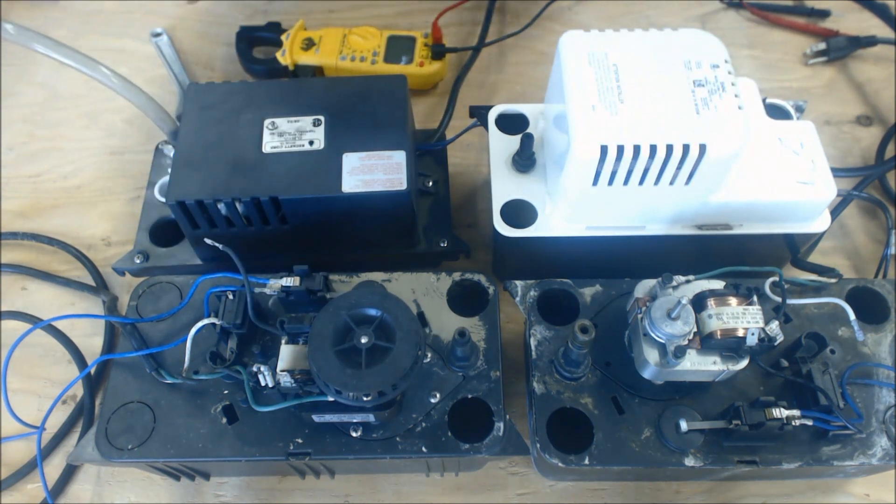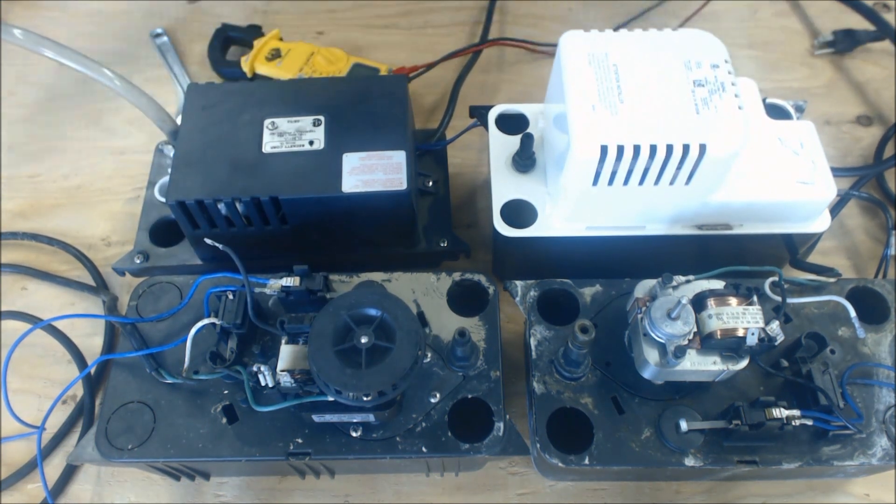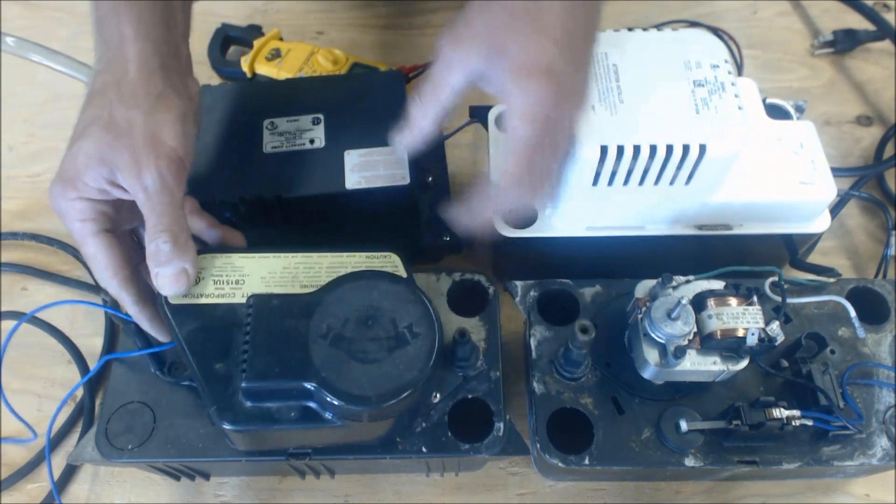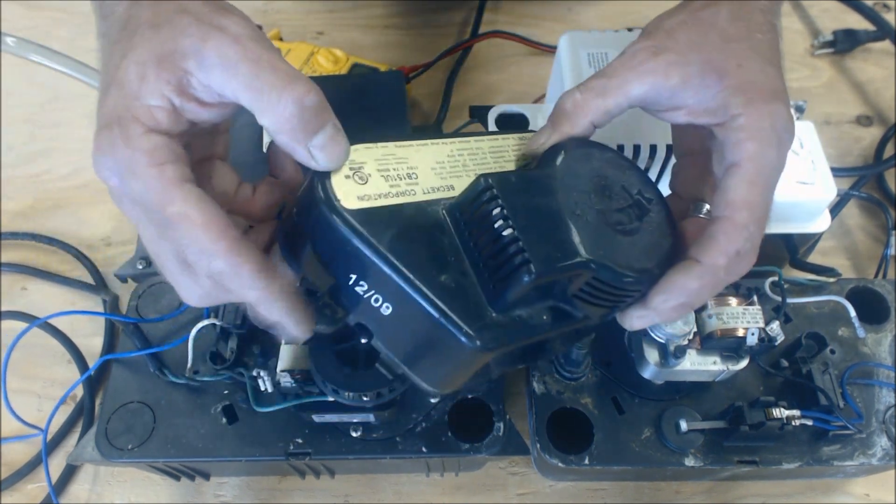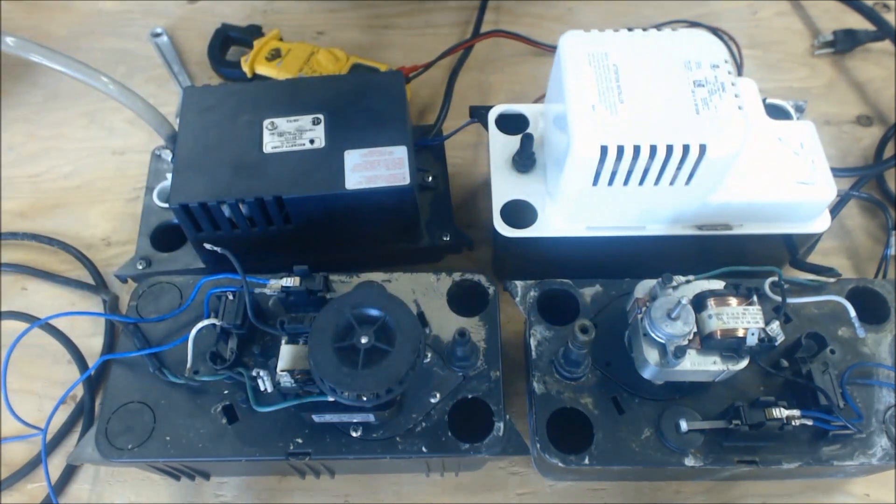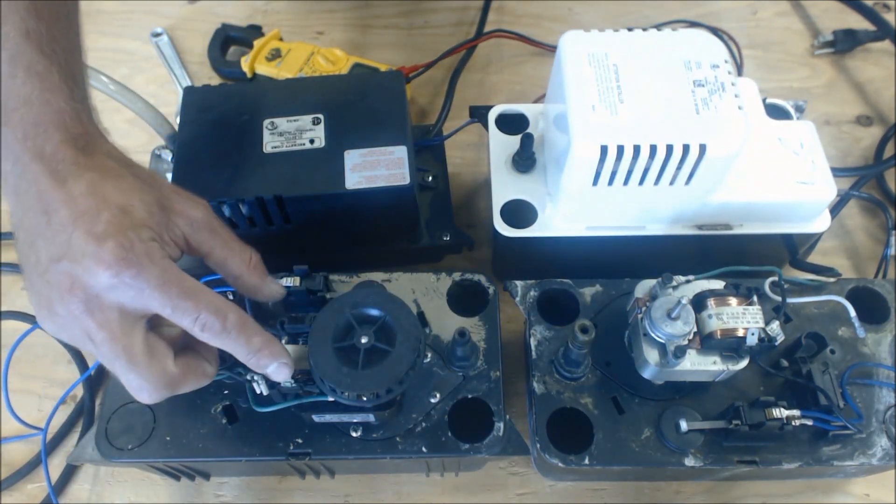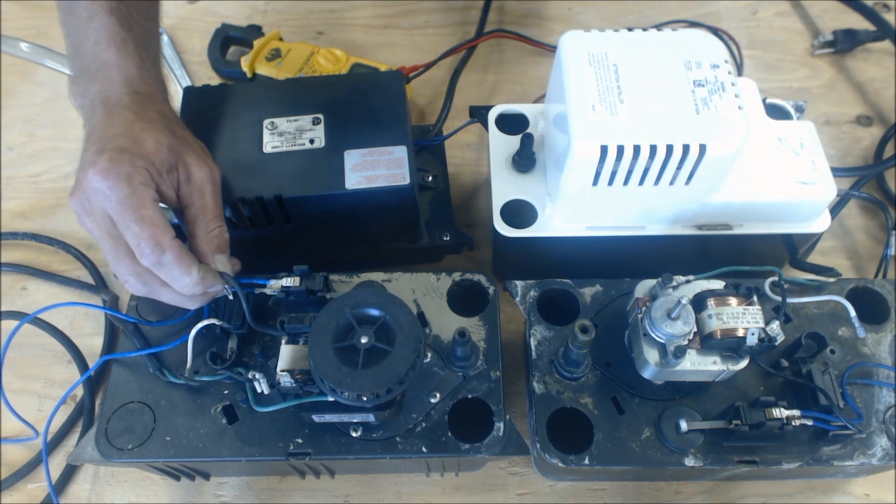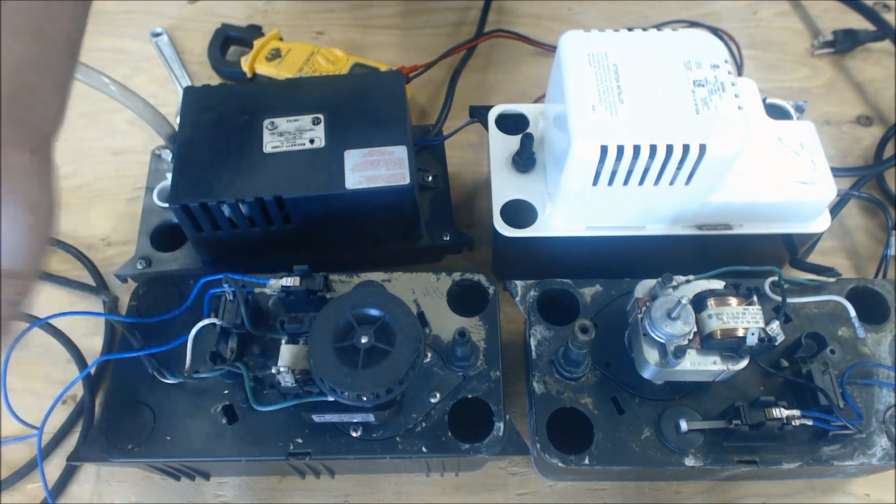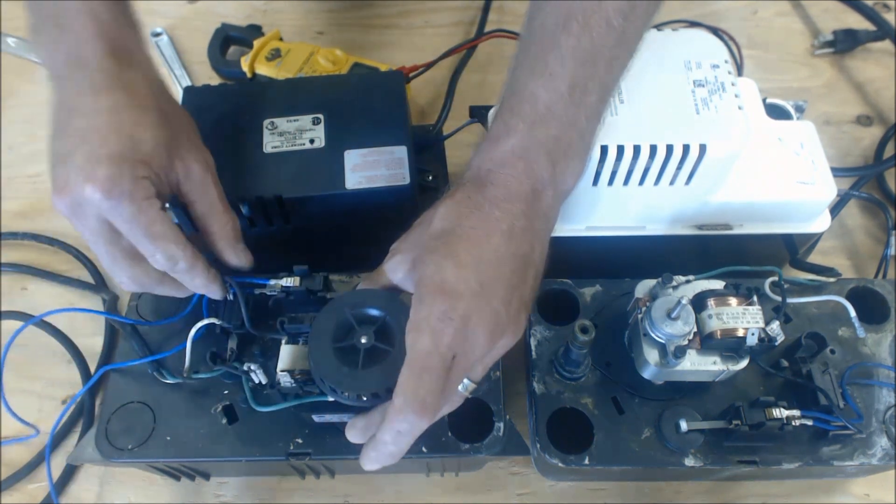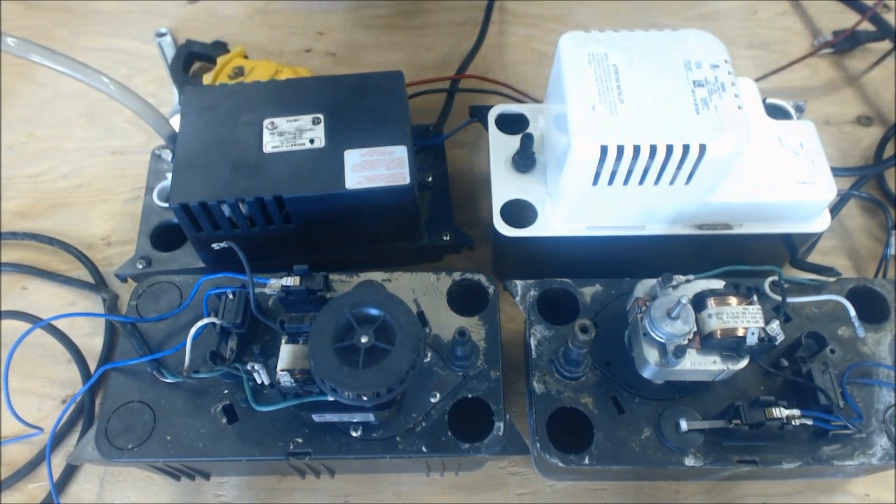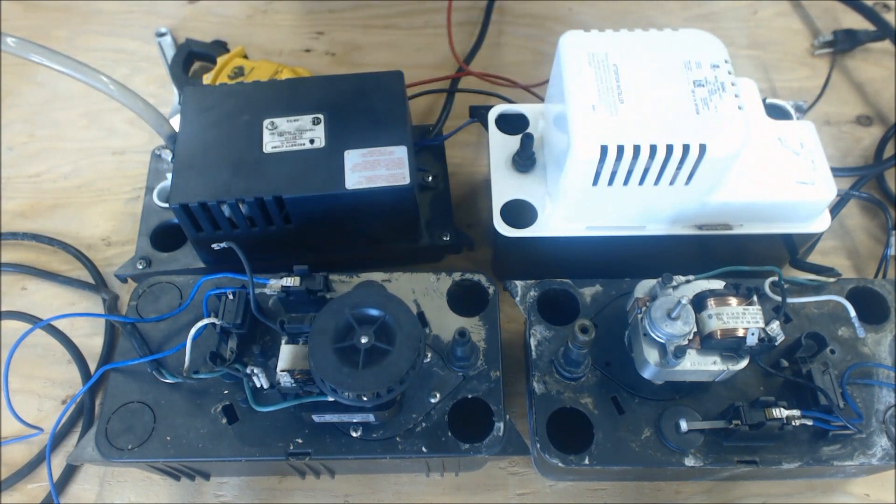So as far as diagnosis on that, you just take this assembly off first, it's just one screw on this one. Just take that off and you isolate your motor. This was right here, so you just go ahead and disconnect those. Obviously you turn the power off then, you disconnect that. What you're doing is you're isolating the motor windings.